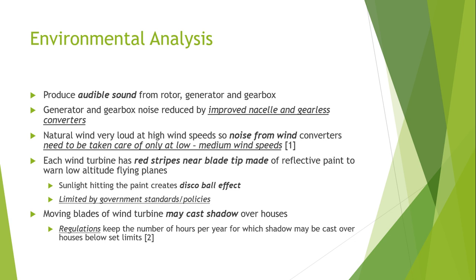Sound emissions created by wind power stations represent an essential parameter for converter siting. A favorable arrangement of wind energy converters and corresponding selection of converter models may allow reduction of sound by approximately 5 to 10 dB at constant power generation. Legislation on noise reduction and associated rules and regulations also force engineers to design wind turbines so that overall noise pollution is reduced to within the range of 5 to 10 dB.